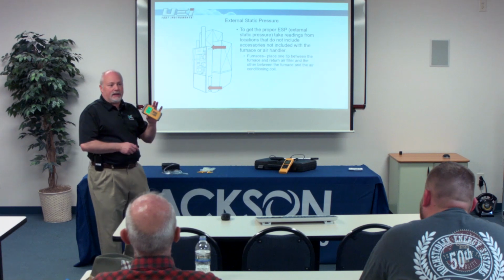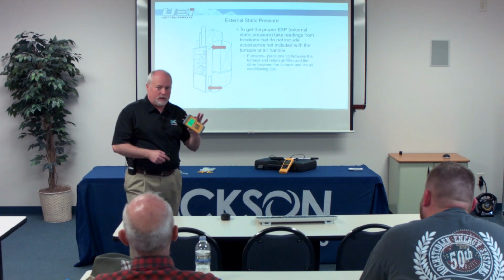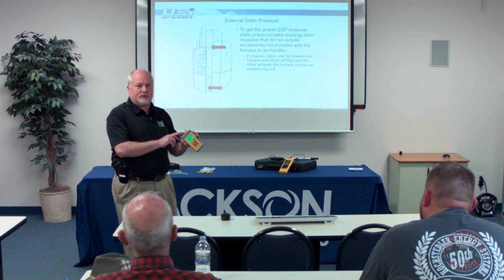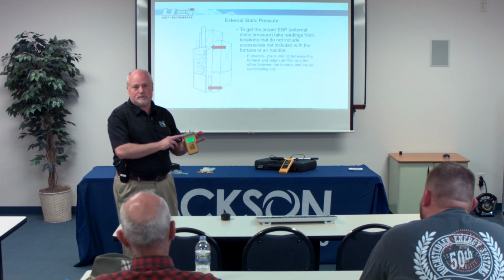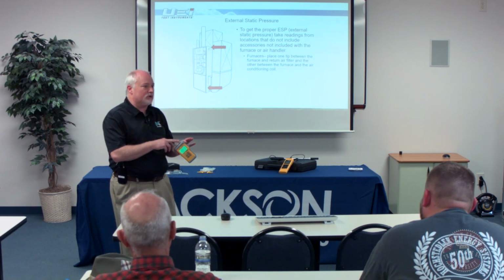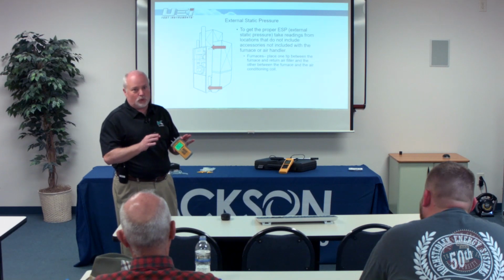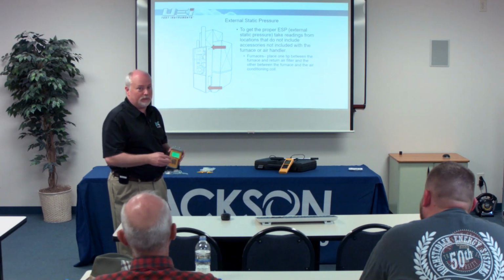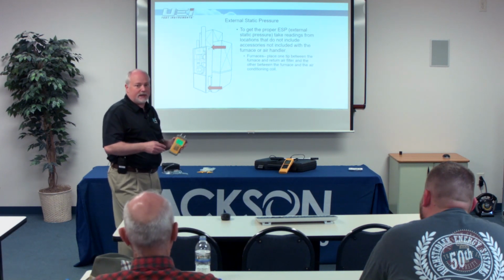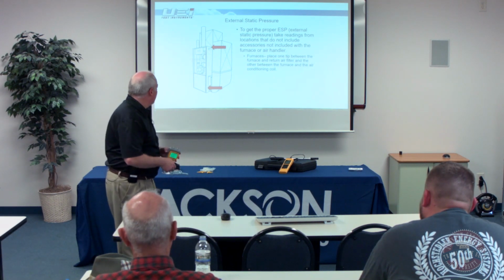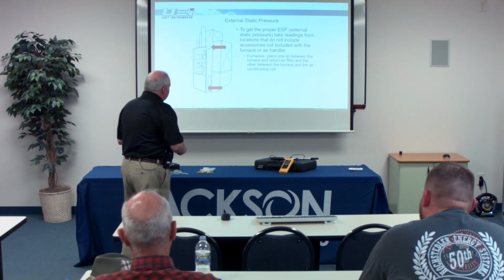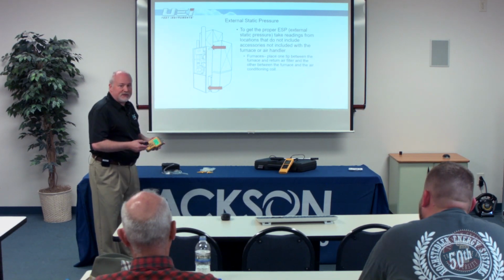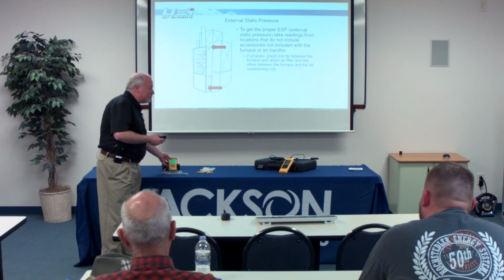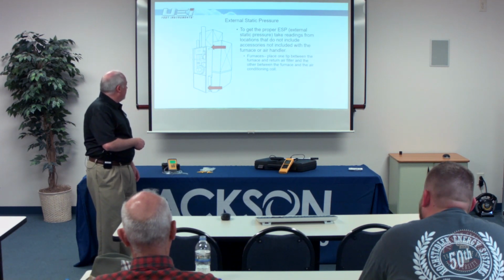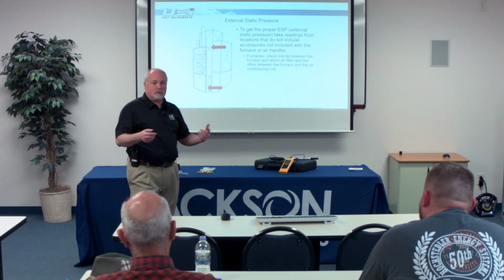If we had a single input manometer, then we're going to take our reading on our supply, write it down. We're going to take our reading on our return, write that down, and we're going to ignore our plus and minus and just add the total. So the total number is going to give us the total external static pressure of that system. Okay? In this case, we're looking at our placement for a standard gas furnace, or it could be an oil piece of equipment. In that case, the gas furnace, our coil's not included.